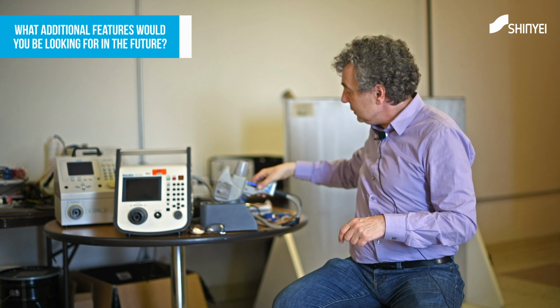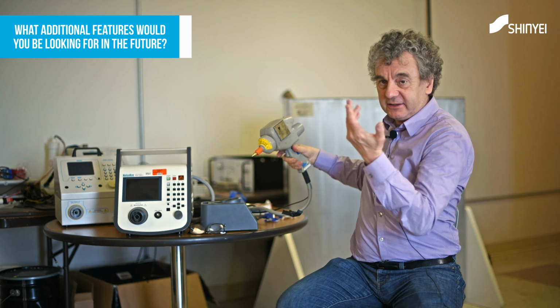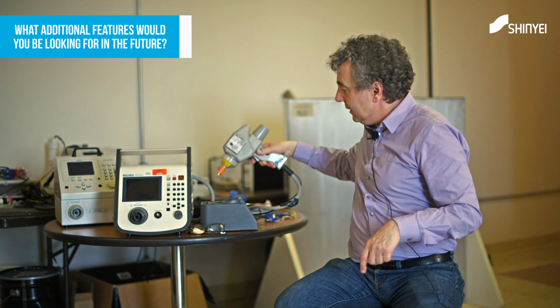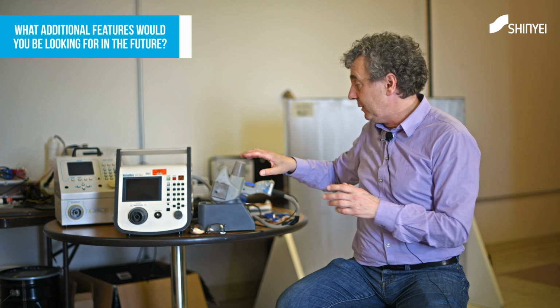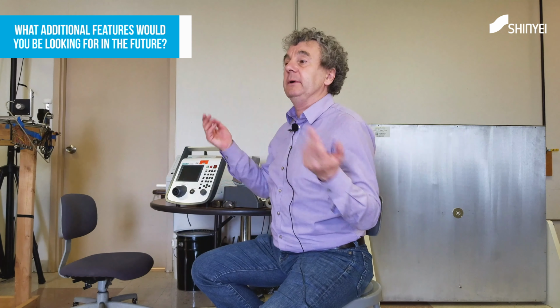So a good ESD lab should have video recording. You record the testing, and then you see, when I discharged at this angle, with this tip, let's say it's air discharge, the unit blinked, and then it crashed. And this is all documented. So the reaction of the unit is documented, and the current is documented. And now, of course, if the DUT did not react, you don't keep it. You just throw it away.